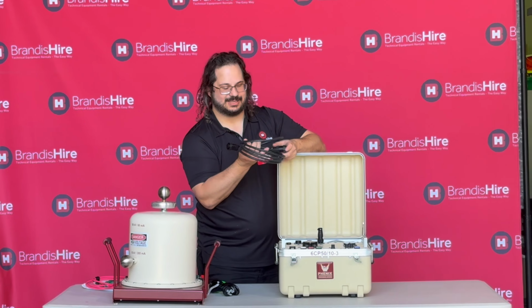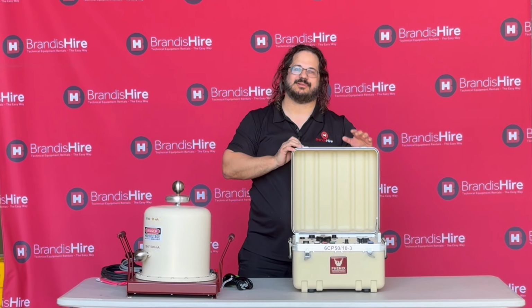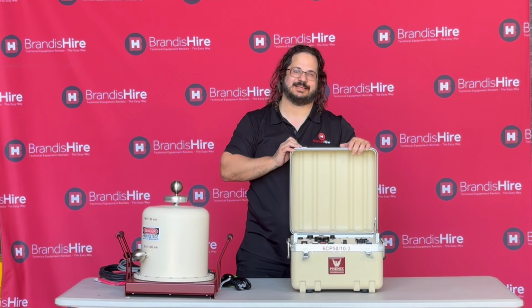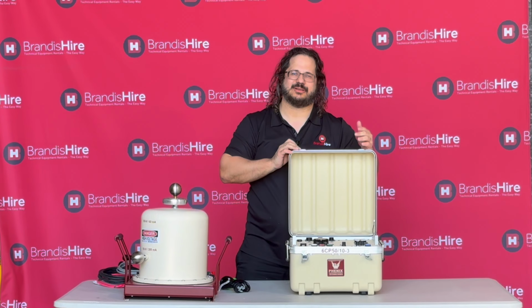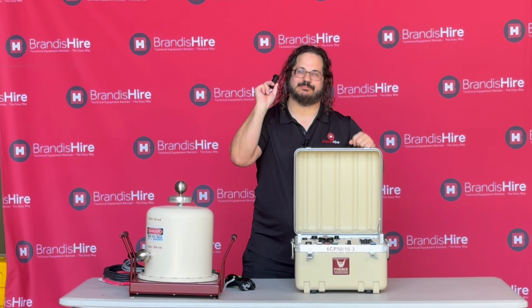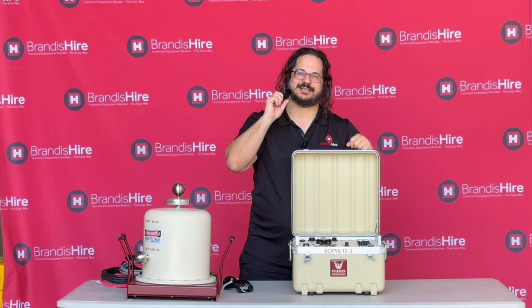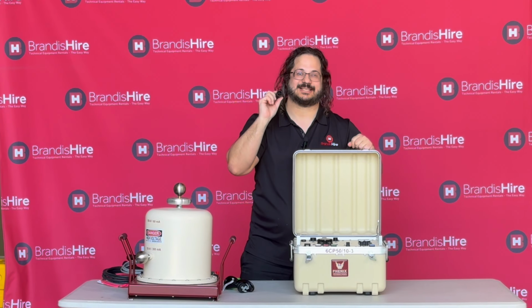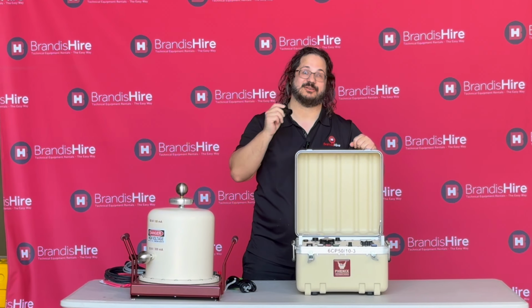That is the safety interlock. So some of these units will come with a foot pedal. That's an important thing to use when you're doing high voltage testing. It's a way of using a dead man switch to make sure that you're operating everything safely. But if you don't have one, you must include the safety interlock. This is the most critical part of all tech support that I do for this unit. Make sure that it's in place, otherwise it won't work.